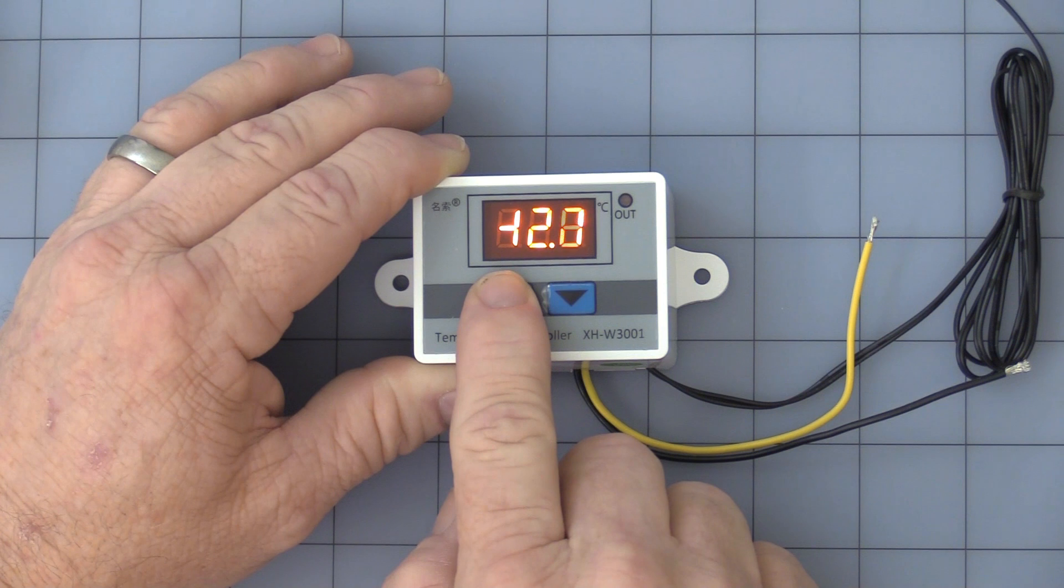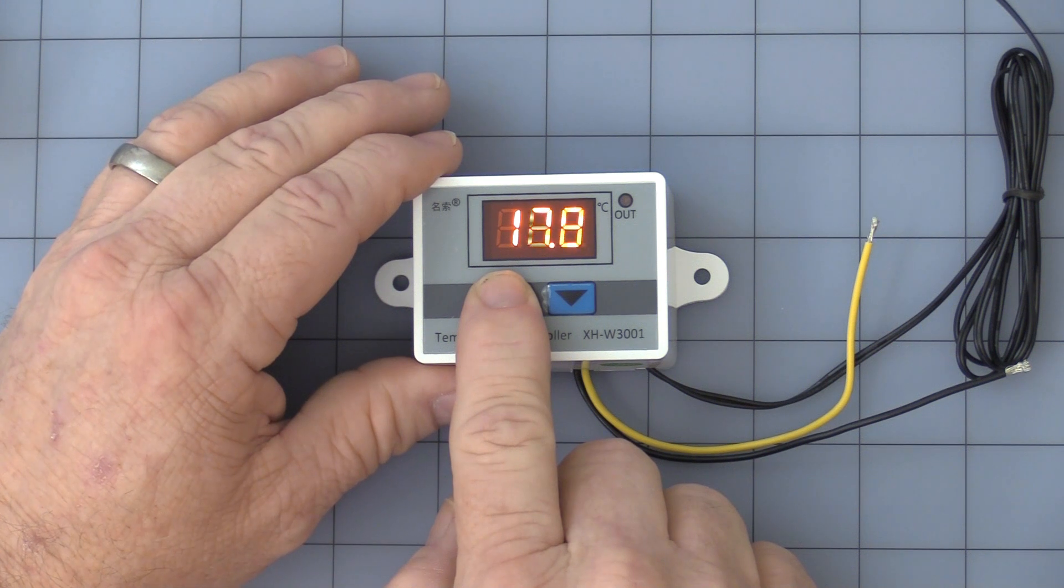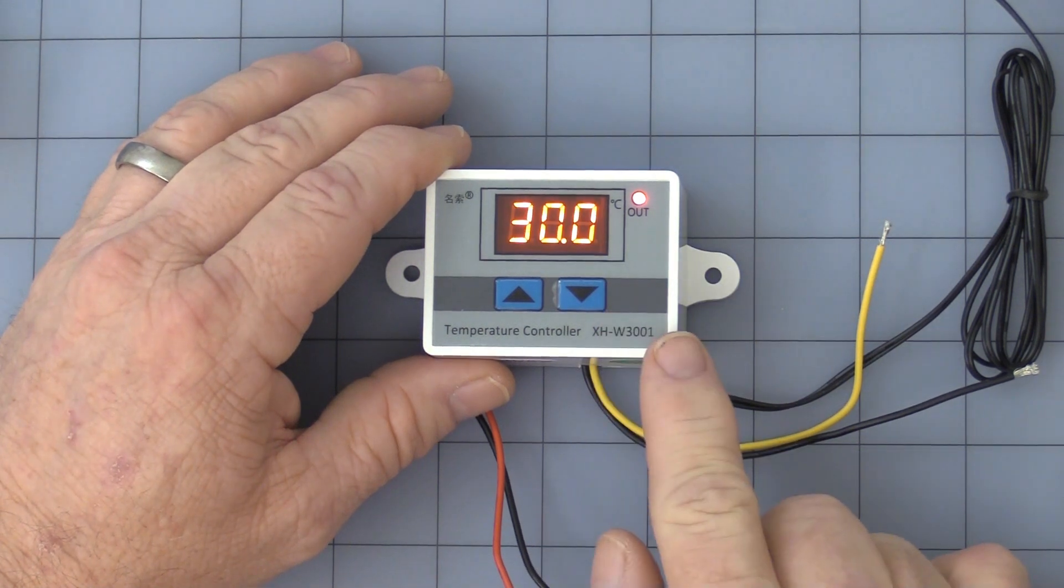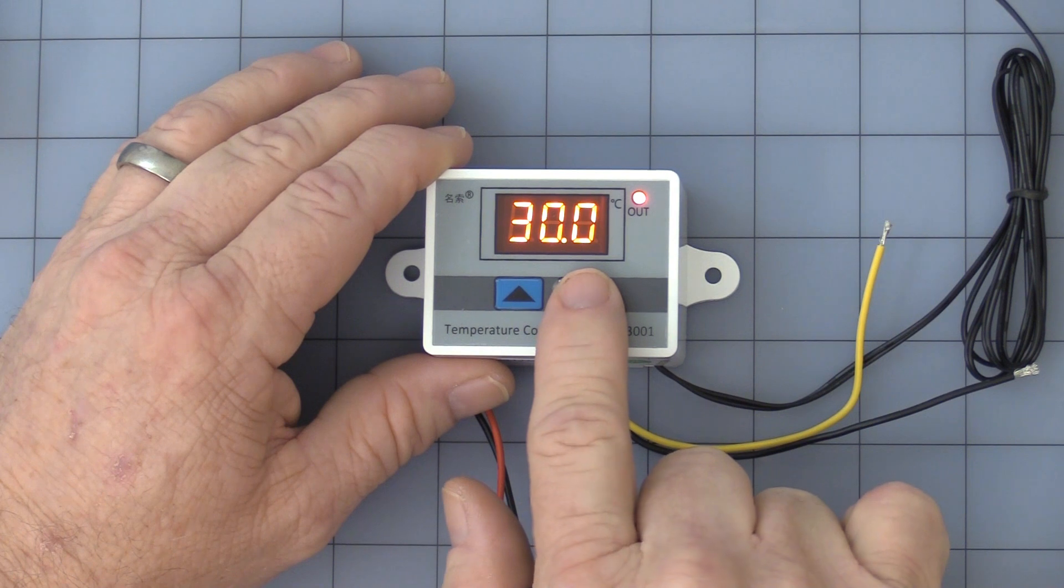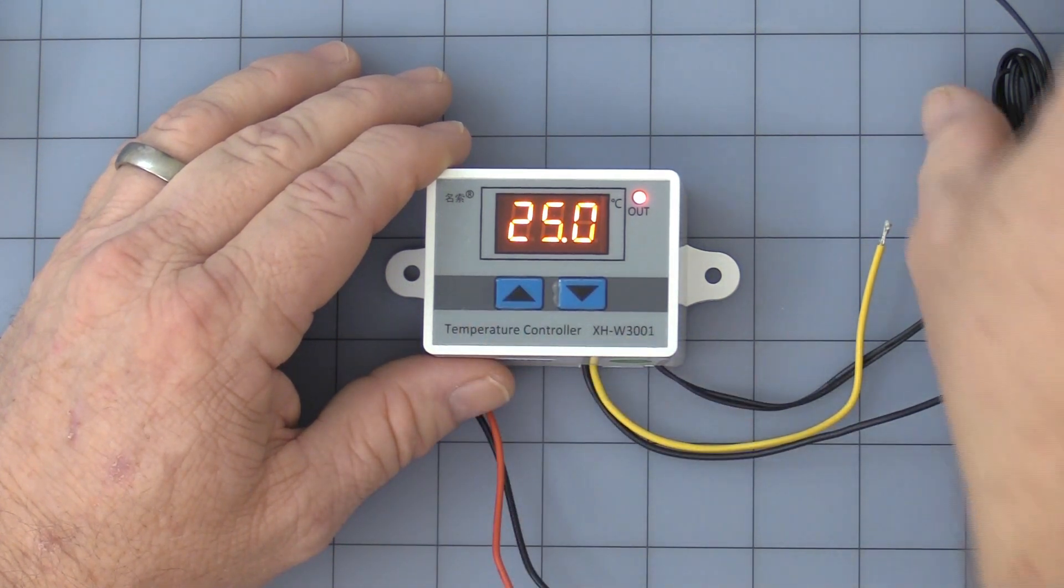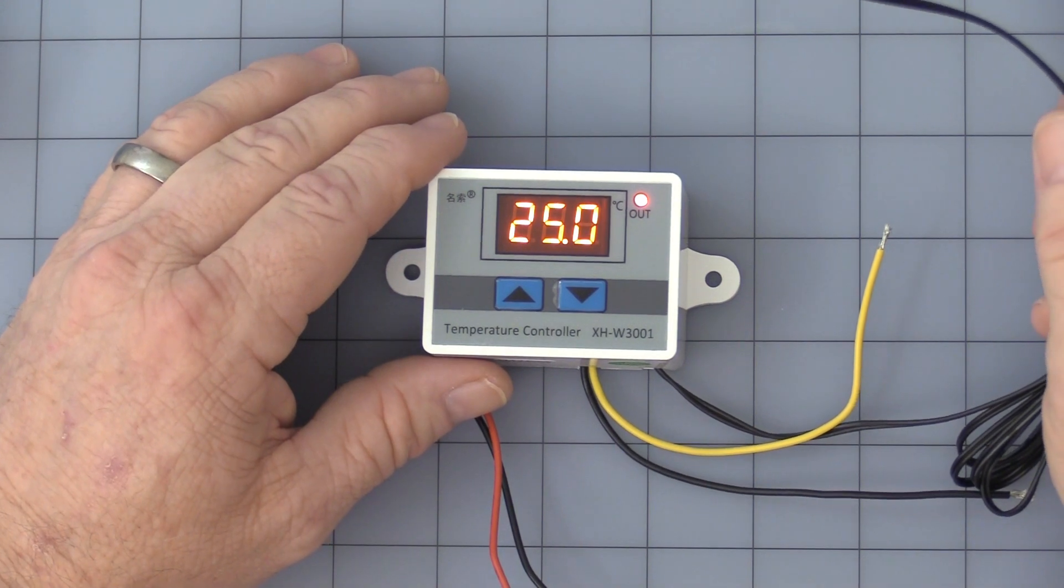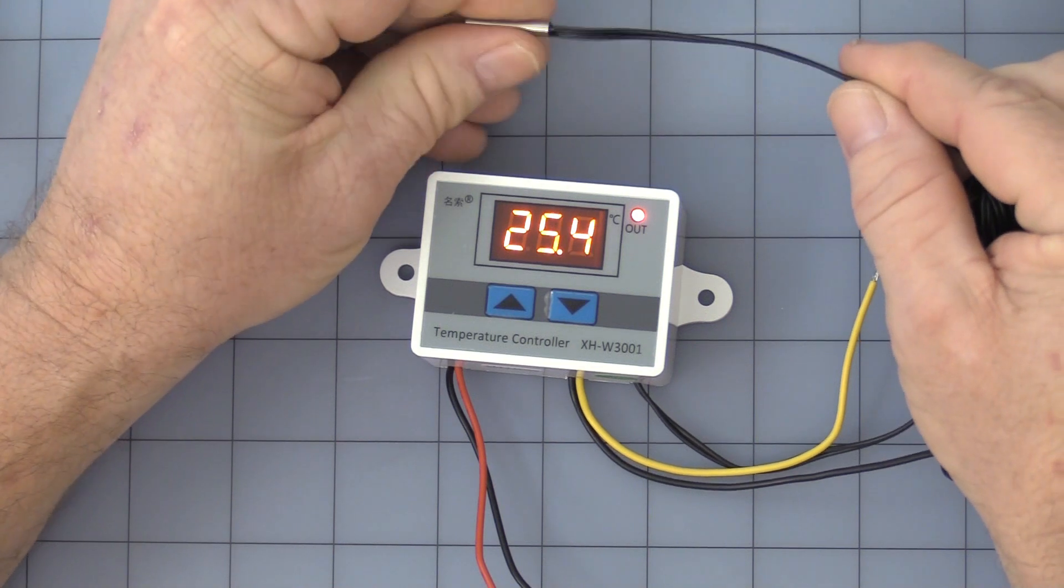But I want to set this at about 30 degrees Celsius just so I can show it operate, how the operations, how it works. And you take single steps. Alright. So this setting, once it stops flashing, that's actual air temperature. Upper end is 30, lower is 25. So this is the heating mode. So when I warm this thermostat up to over 30, it should turn the relay off.